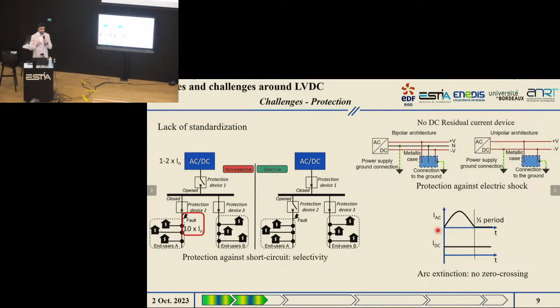The third challenge we can highlight is the difficulty around arc extinction. If we compare this phenomenon in AC, we observe a periodic zero crossing of the current, which does not naturally happen in DC. This means it's a lot harder to interrupt a fault in DC than in AC for protection devices.